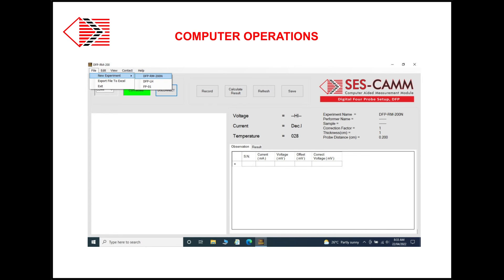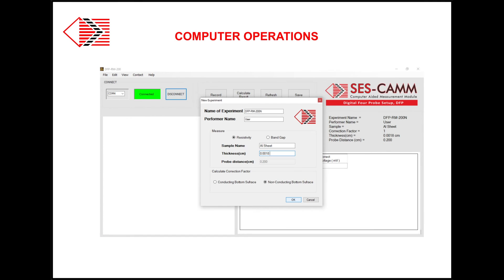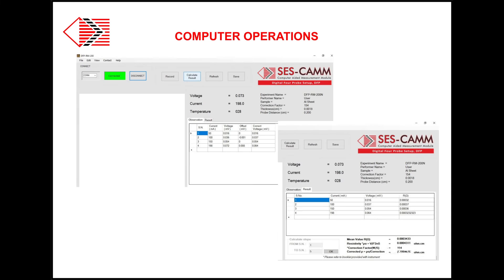Further, fill the required information as it appears in the dialog box. Here, just to show the variety, we will do measurement on aluminum sample. If the resistivity measurement option is selected, a dialog box will open requesting further information of the sample. Feed all required information and click OK. Now set an initial current to say around 50 milliamps and record the corresponding voltage reading by clicking on Record option. Raise value of current till 200 milliamps and keep on recording the voltage values. Finally, click on Calculate option to get final results. Save this table and results in an Excel file.